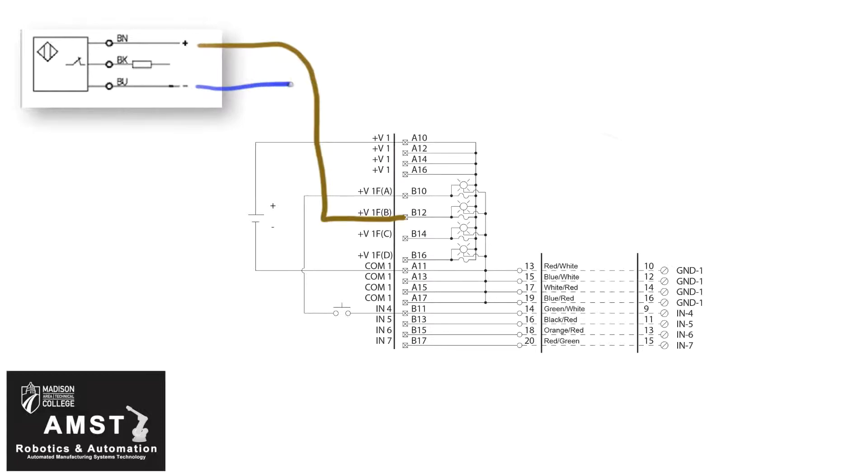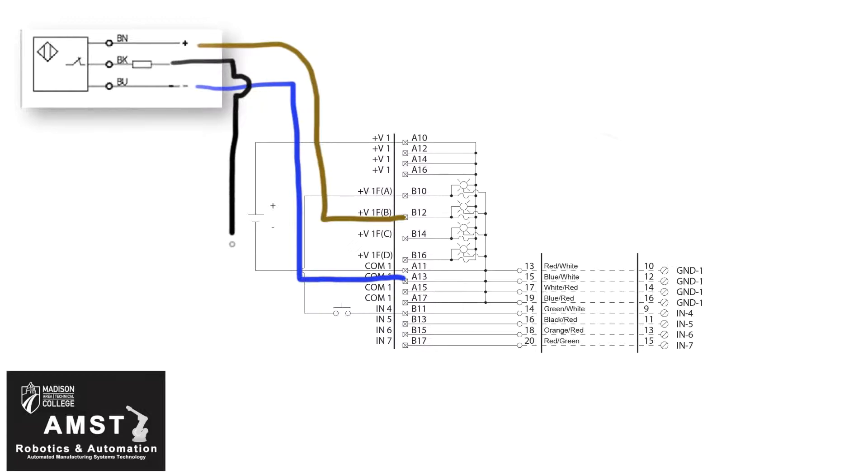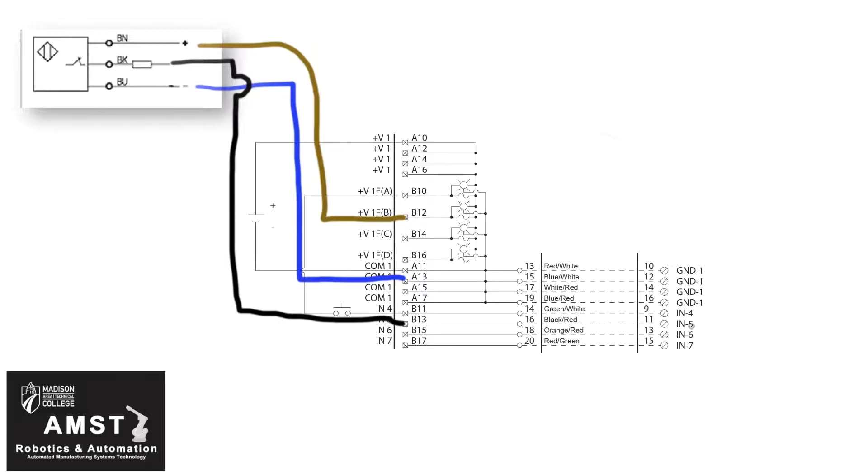The negative lead is going to connect to A13 on the terminal strip. And then the third wire, the black wire or signal wire, is going to connect to the next available input on the IFM, and that is B13, which ultimately connects to input 5 on your PLC.